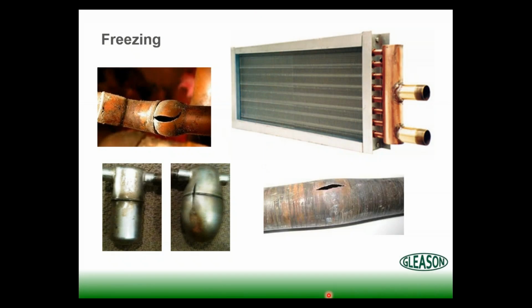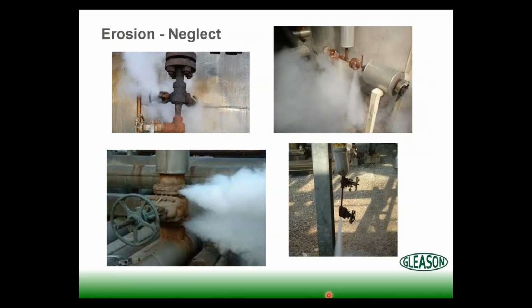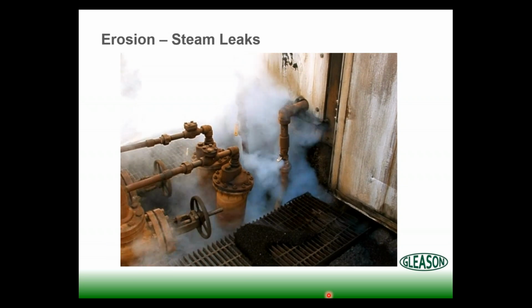And some other perceived negatives here. Freezing. Again, we need to make sure we pipe things properly, and freezing won't be an issue. Erosion can be a problem. We see an awful lot of neglect in steam systems. I heard one guy say to me about a month ago, "Yeah, I've been here about 12 years. That thing's been leaking ever since I got here." Well, we need to pay attention to that, because as those leaks erode, that steam will erode the metal, and the leaks will get larger.